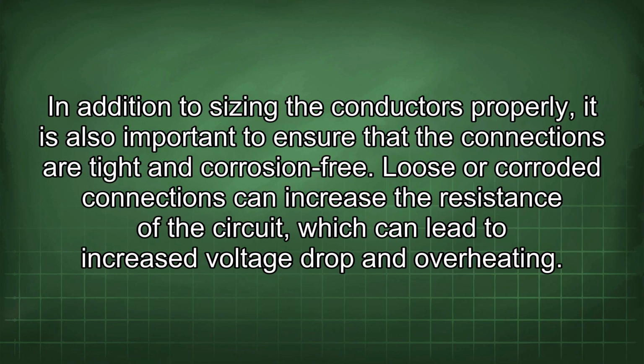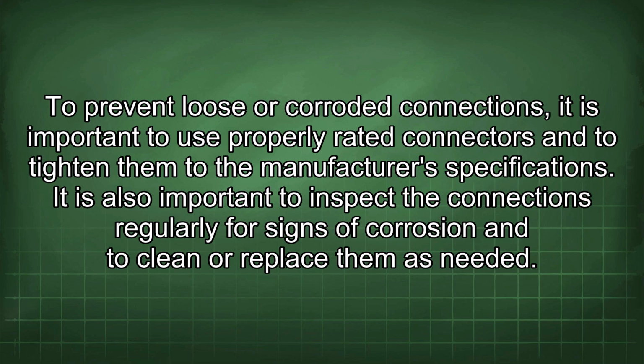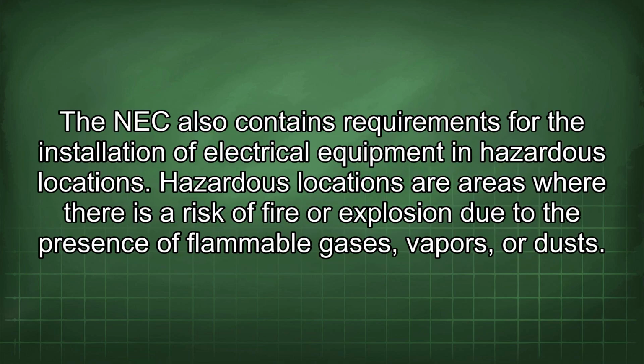In addition to sizing the conductors properly, it is also important to ensure that the connections are tight and corrosion-free. Loose or corroded connections can increase the resistance of the circuit, which can lead to increased voltage drop and overheating. To prevent loose or corroded connections, it is important to use properly rated connectors and to tighten them to the manufacturer's specifications. It is also important to inspect the connections regularly for signs of corrosion and to clean or replace them as needed.